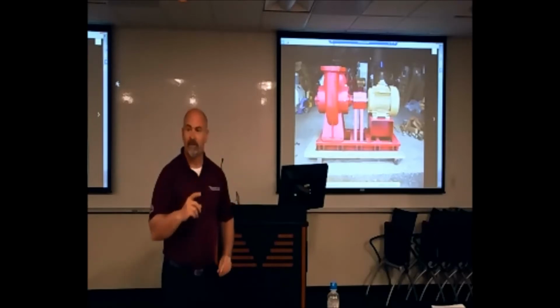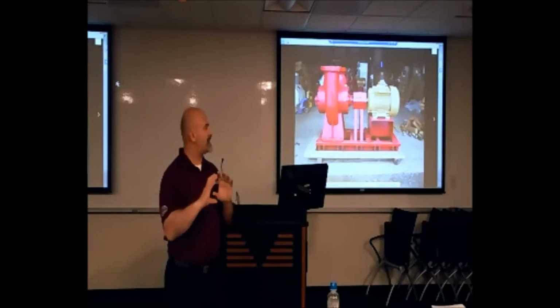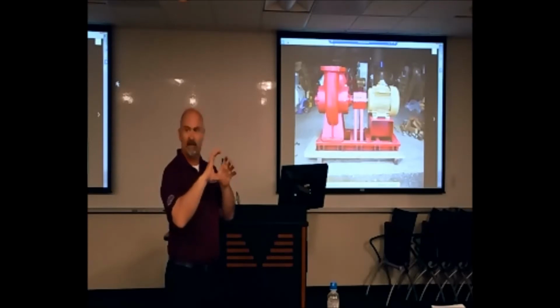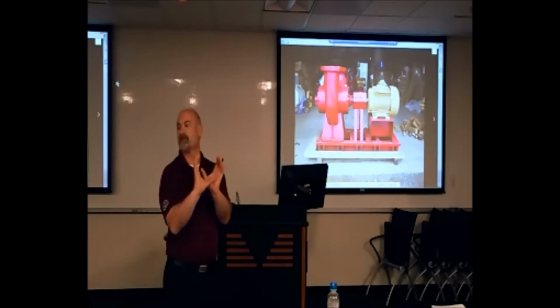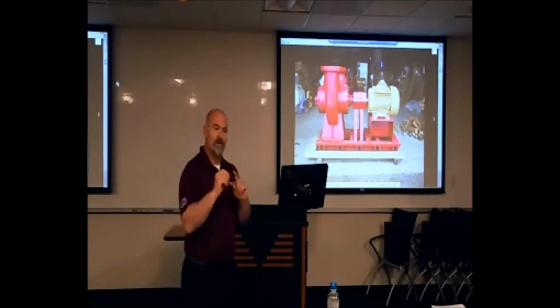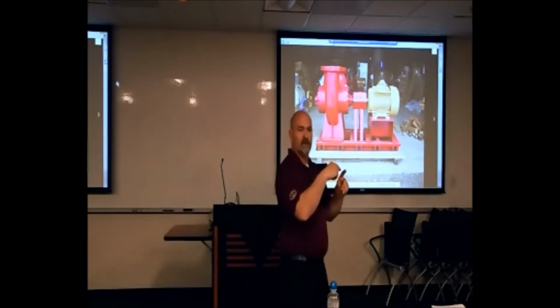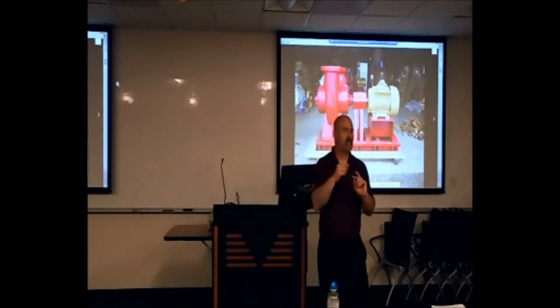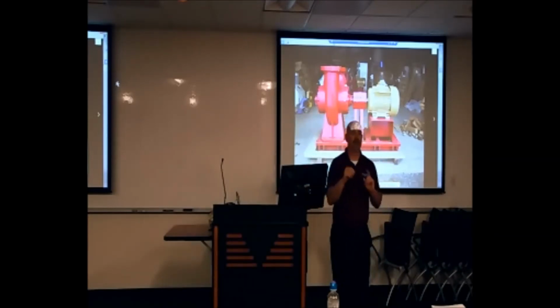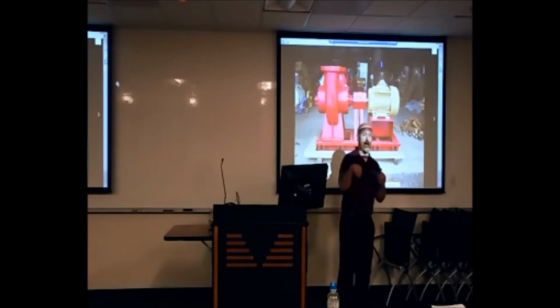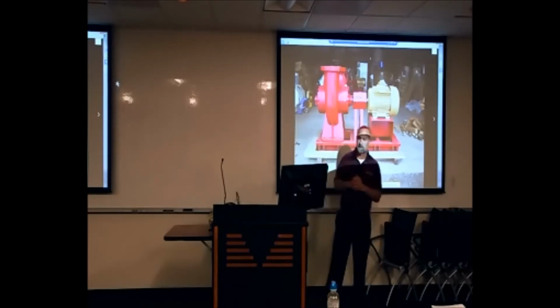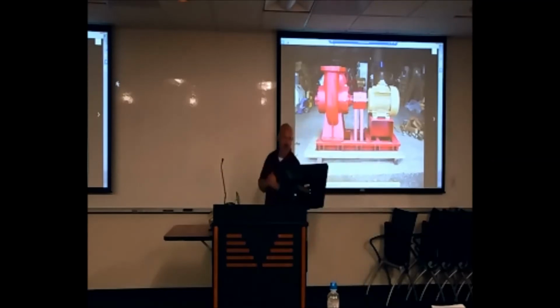Key thing though, now that we're no longer going inside, in the past we usually just slipped inside and that coupler just stuck in there. There was nothing holding it in other than the fact that the coupler halves are coming over the top of it. With this design now, there are 3 bolts on each one of the coupler halves. Each of those bolts needs to be torqued. And there are torque references in the IO&M that talk about how much torque that's going to be, depending upon the size of the pump that you're dealing with. We recommend that you torque those down after you install them, simply so that it doesn't fly apart when it starts spinning.